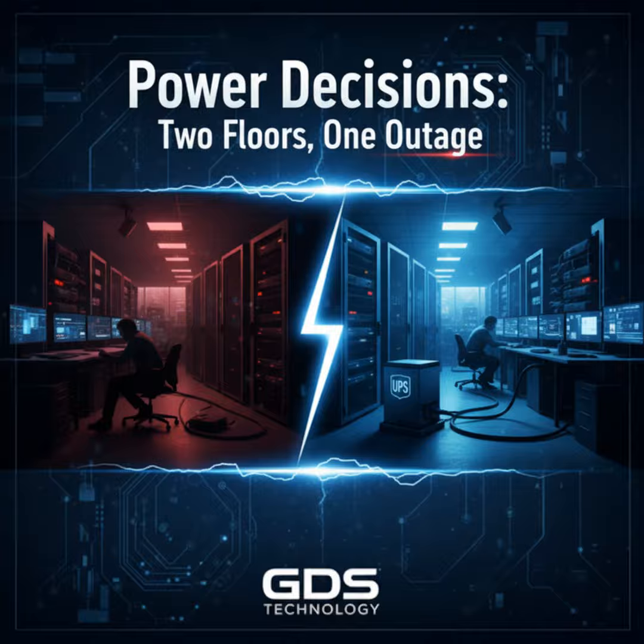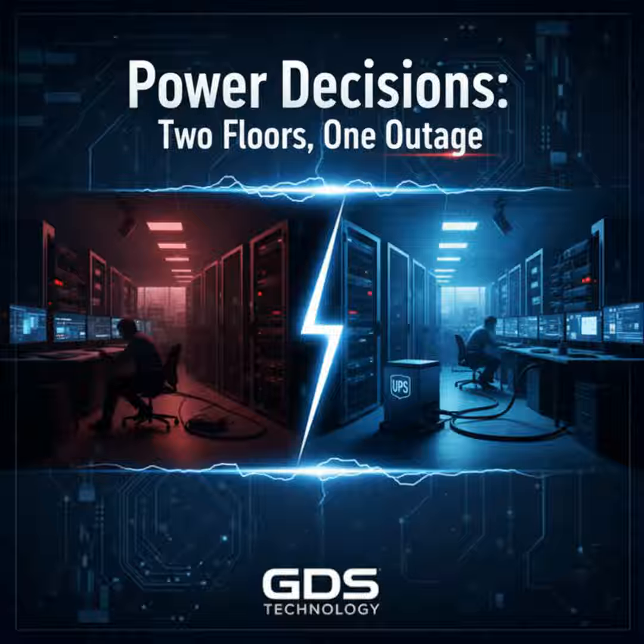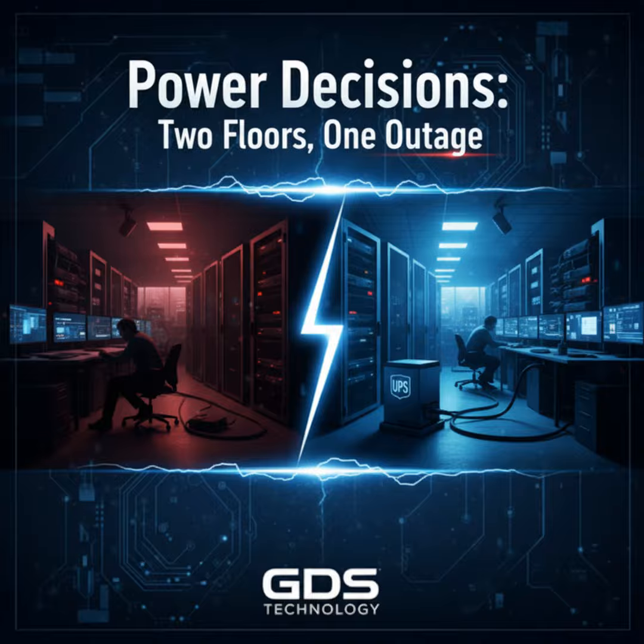If you're already thinking what caused this to go wrong, the short answer is this cluster: undermetering, mixed tenant loads, and ownership ambiguity. Undermetering hides true demand. Mixed tenant loads, where tenant-provided equipment is mixed on building panels, makes it hard to isolate critical circuits. And when nobody's accountable, maintenance and tests fall through the cracks. Those 3 root causes show up again and again in the field.